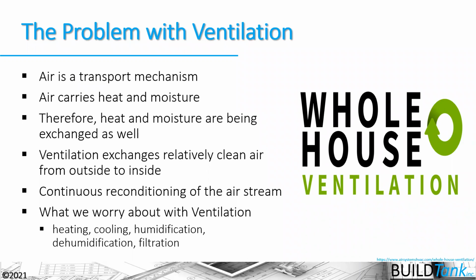We are also needing to condition the air that we're bringing into that house. So there is an energy penalty associated with ventilating a house, because we're exhausting air out of the house, or we're taking air out of the house and replacing it with relatively clean air from the outside, but that air isn't conditioned. It hasn't been cooled or it hasn't been heated. So we need to continue to do that. So we worry a little bit about ventilation from a heating, cooling, humidification, dehumidification standpoint, depending on the climates that you're in, and also the ability to filter that air.